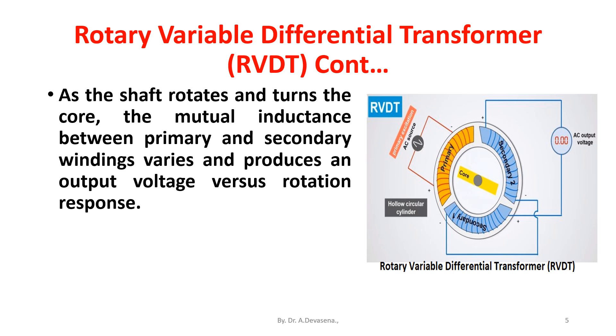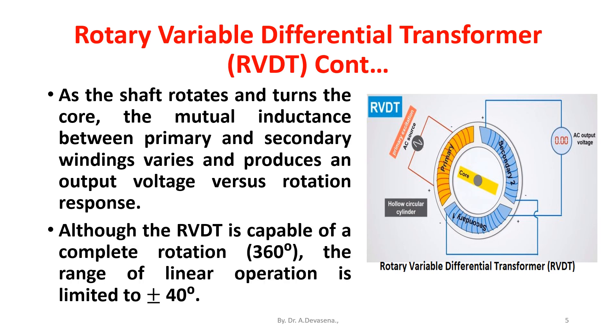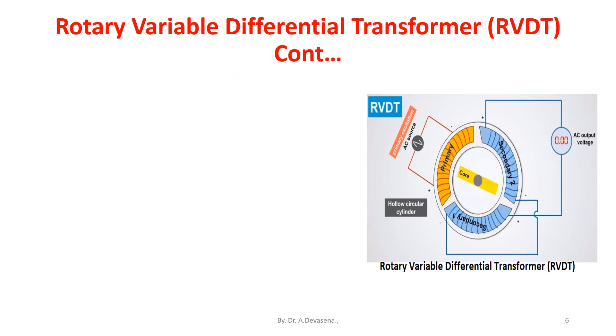Although the RVDT is capable of a complete rotation of 360 degrees, the range of linear operation is limited to plus or minus 40 degrees. The linearity of a typical RVDT having a range of plus or minus 40 degrees is about 0.5 percentage of range.